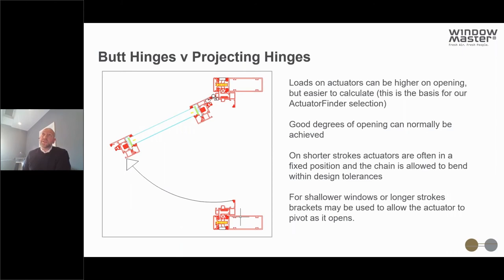Butt hinges versus projecting hinges: with butt hinges the loads on the actuators are easier to calculate. The forces required tend to be a bit higher but we know what they are, and that's the basis on which the actuator finder works. We can normally achieve good degrees of opening. On shorter stroke applications the actuators may be fixed and the chains are designed to bend with the arc of the window opening. On longer stroke applications we may use an actuator with a longer chain and a pivot bracket which allows the actuator to pivot and tilt as the window opens.